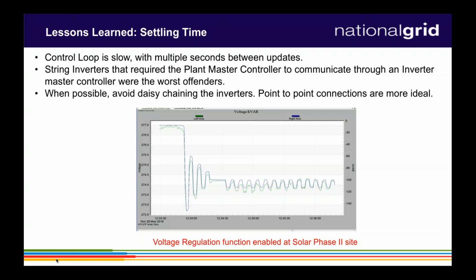And here, when we have a volt var function, you turn it on, it sees a certain voltage, so it's going to react with a certain amount of vars. Then the voltage drops because you are reducing it by absorbing some vars, and then the system calculates, oh, I need to stop absorbing vars because the voltage is low, and then the voltage jumps up, and you end up with this ringing. So what you thought was an improvement to your power quality or your voltage profile by turning on an advanced inverter function really ends up being a detriment to power quality on the system.